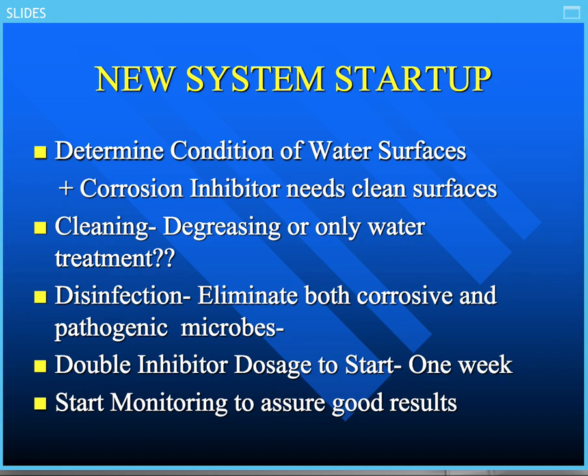The key here is you must disinfect your new water system. Usually using a high level of chlorination or bromination. Both of those work very, very well. Chlorine dioxide works quite well as well. And the key here is to have good dispersion to make sure you get rid of all of these corrosive organisms and all microbes, and that you can actually kill those. Follow that, of course, once you clean the system up, you must double the inhibitor dosage for about one week or so at startup, so that you actually are starting to protect your system very effectively.